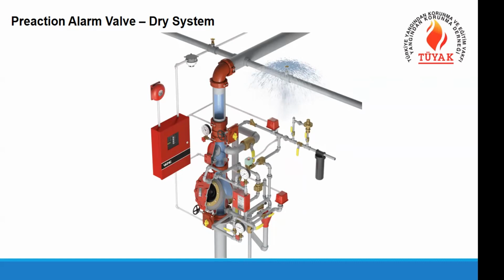So for example, somebody hit the sprinkler and we don't have any fire in the room. Somebody hit the sprinkler by accident and it's open. So we have a very important room, historical records or archives or very expensive devices inside the room. So if somebody accidentally hit a sprinkler, there should not be any water coming out of the sprinkler by accident, because it will be more harmful than fire to the documents inside or to the devices that we protect. So it should be a pre-action system.